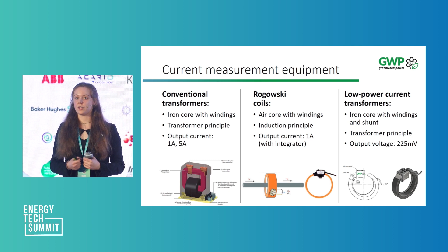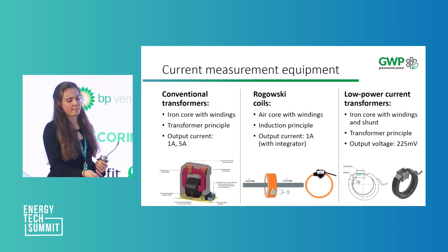Again, the principles are a bit different. For example, the conventional transformer still implements the transformer principle. The Rogowski coil has an air core, and the low-power transformer also has an iron core, but with a shunt resistor, so that the output signal is very small and nice for all the engineers in the field, so they don't hurt themselves. Again, let's look first at energy efficiency.